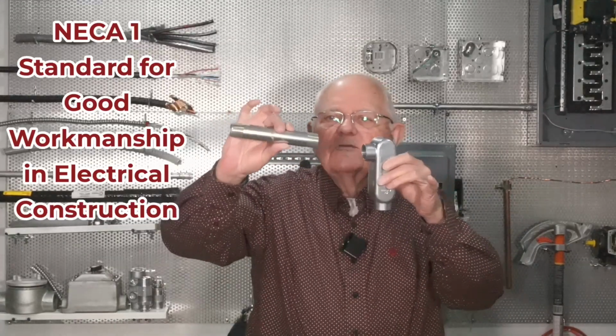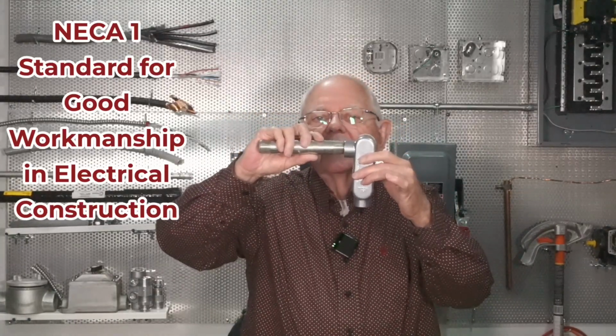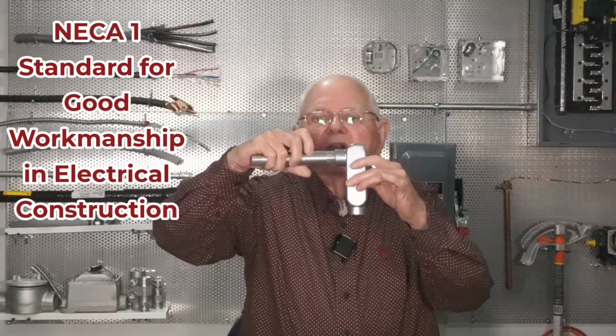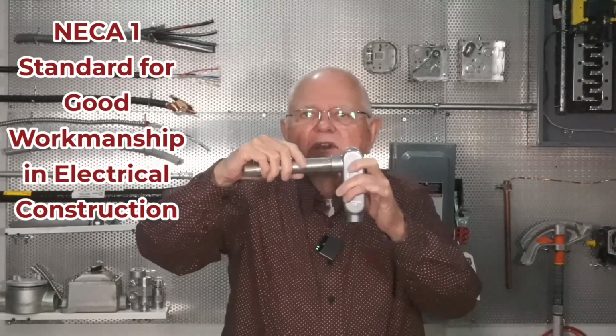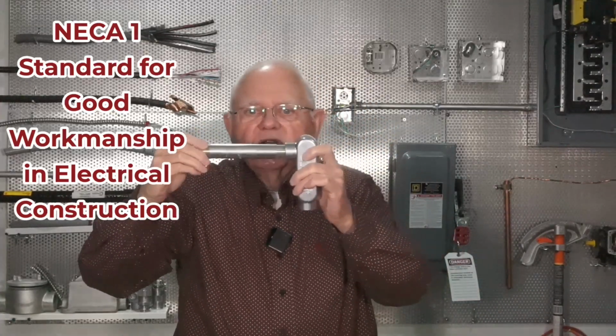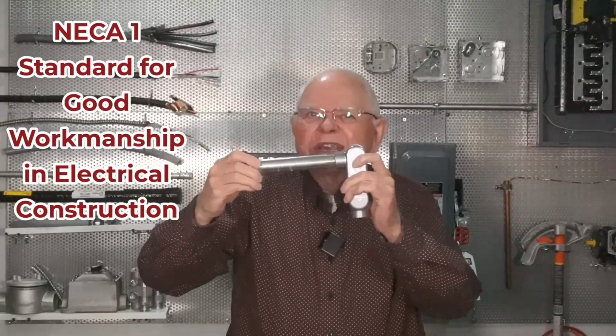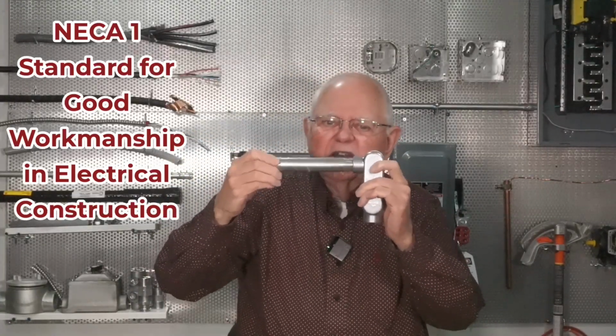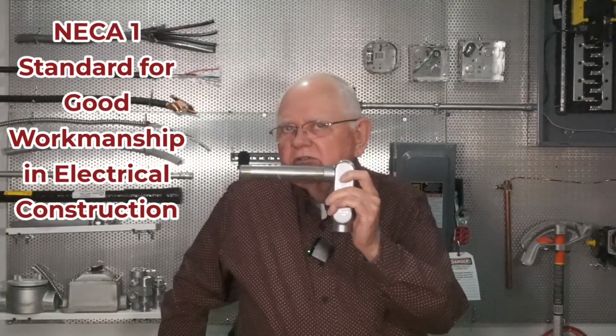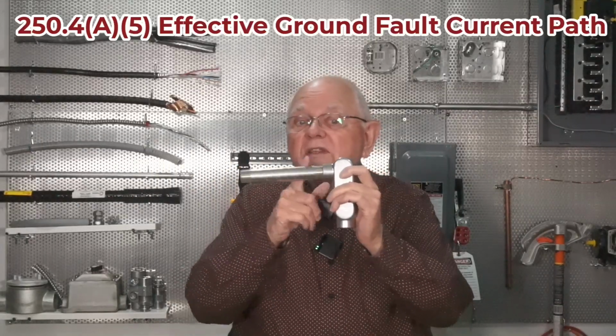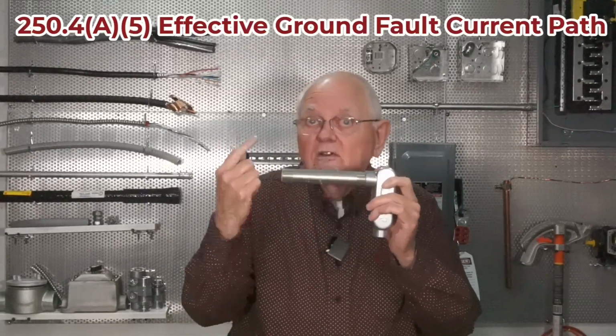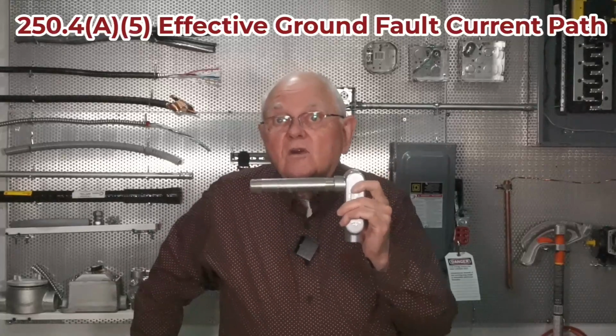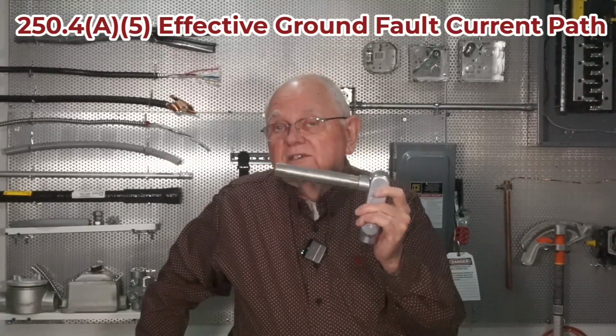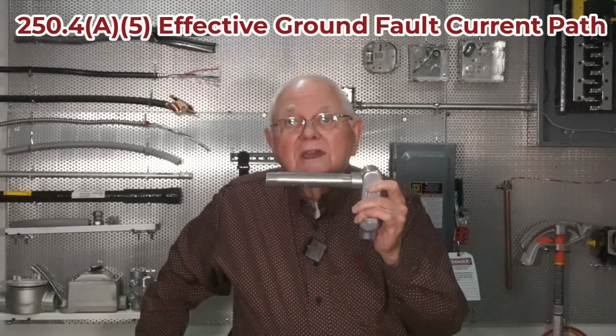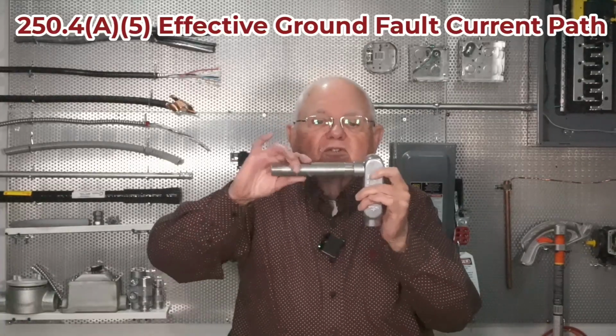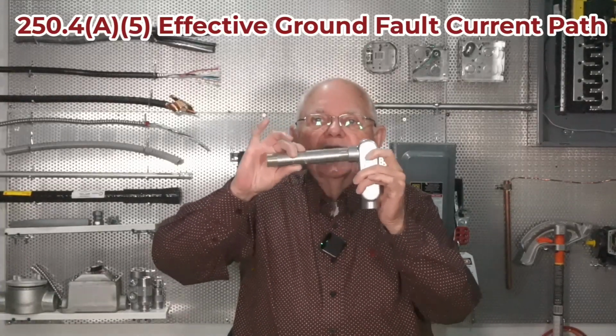So if I take tapered threads, which are tapered on the end, and I start to put them into those straight threads, if I were to leave that connection like that, I've got a loose connection. Mechanically, that's not good. That's not very sound. But there's another issue. In the event of a ground fault, this conduit has to carry current all the way back to the source in order to allow the overcurrent protective device, the circuit breaker or fuse, to operate and de-energize my circuit for me. So I definitely have some high resistance at this point.